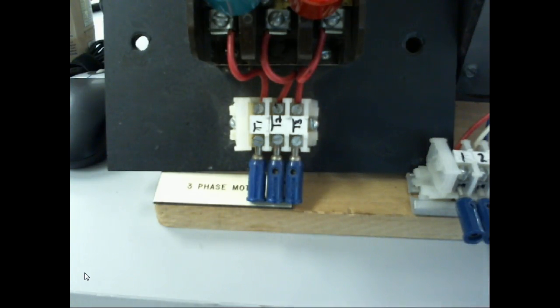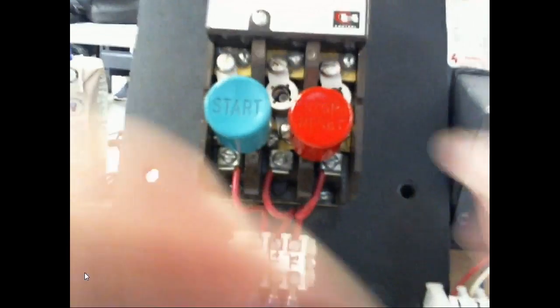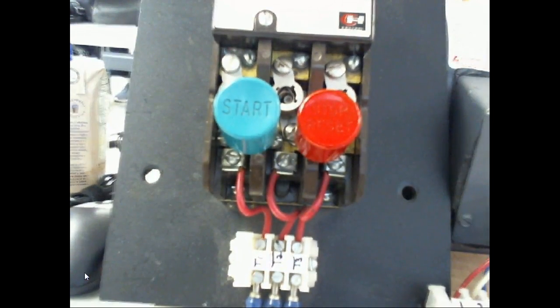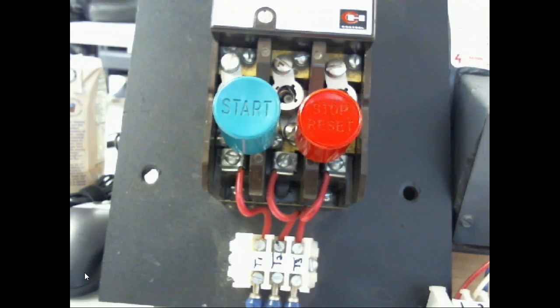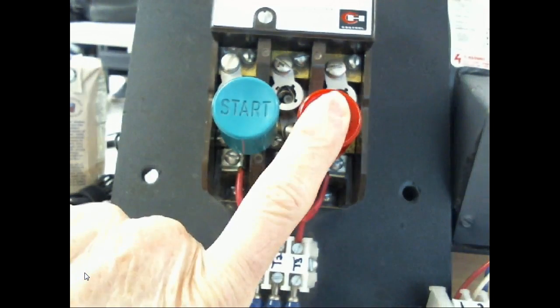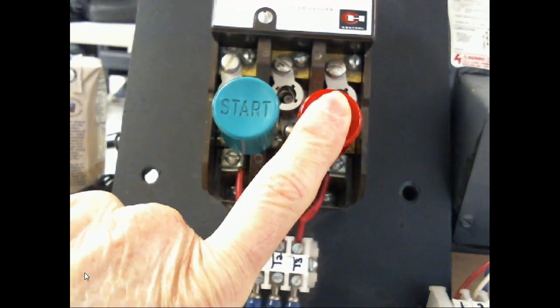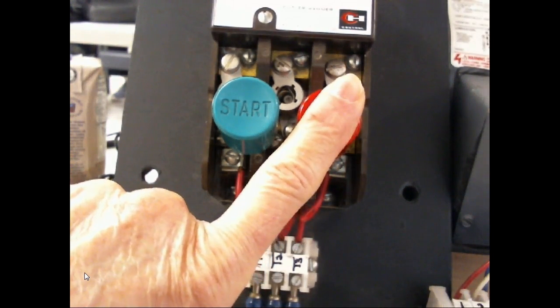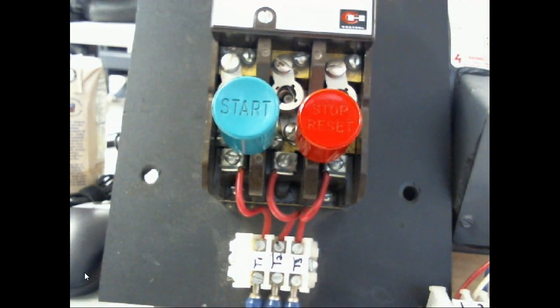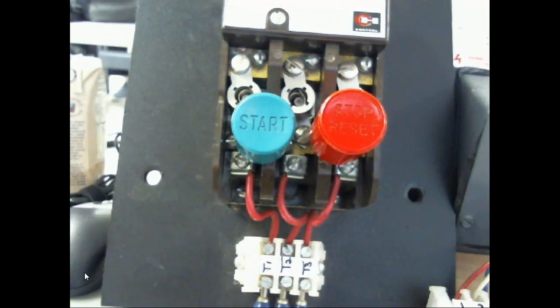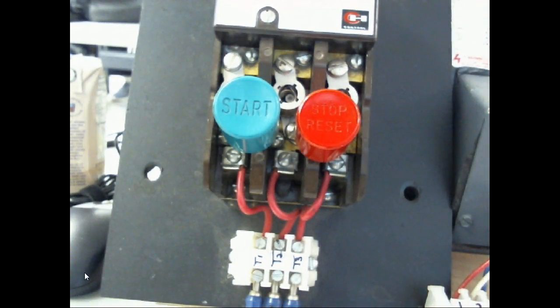Press the start button and read the voltage. Press the stop button real fast. If something happens and you can't get it fast enough, just hit the stop button. You don't have to kill the power, you're working on a powered up circuit. You've got everything done. I've checked it off, right? You understand. Hit the stop button. Don't hit your e-stop unless you need an e-stop, right? And then get yourself oriented, get right, and then hit the what? Hit the start button again. If you can't get it done fast enough, do what? Hit the stop button. And we're going to measure between all phases.